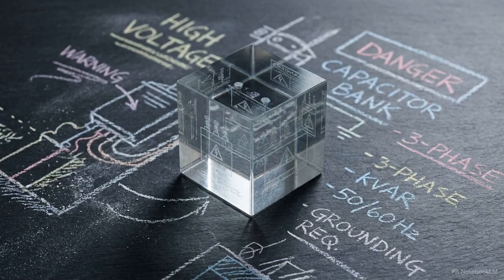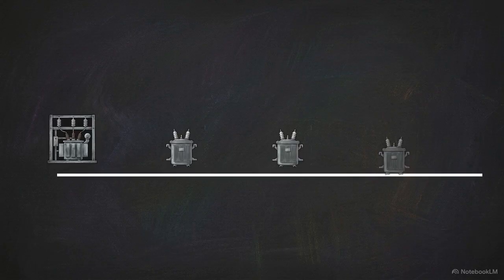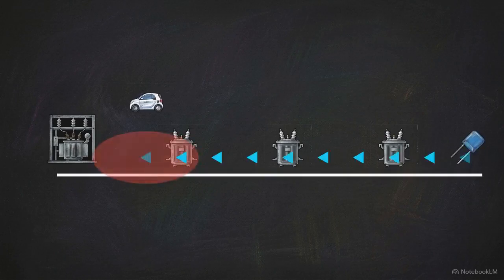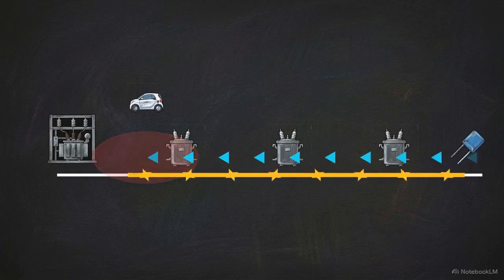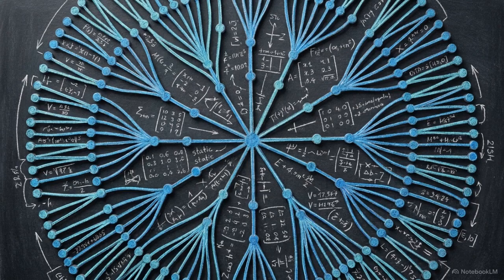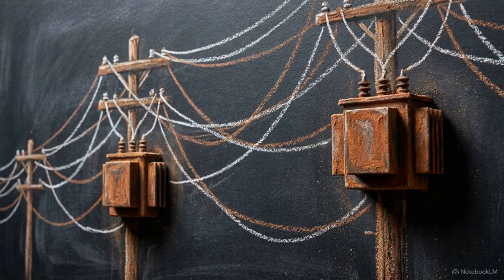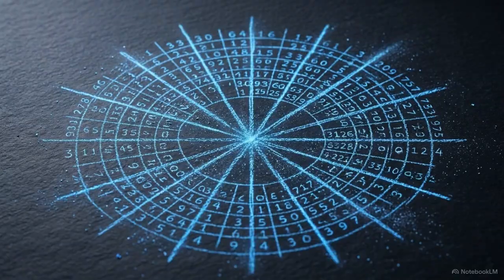Traditionally, utilities rely on statically placed capacitor banks to prop up voltages. But under variable EV loads, pockets of stress physically move along the feeder. A capacitor placed to solve yesterday's low-voltage node might end up pushing reactive current upstream and increasing system losses today. Mitigating these surges is a highly complex optimization problem, calculating exactly how to control the reactive flow across dozens of interconnected nodes. As modern distribution networks face dynamic, unpredictable EV charging loads, rigid deployment strategies become structurally inadequate. The hardware must be guided by algorithms that adapt to the load.